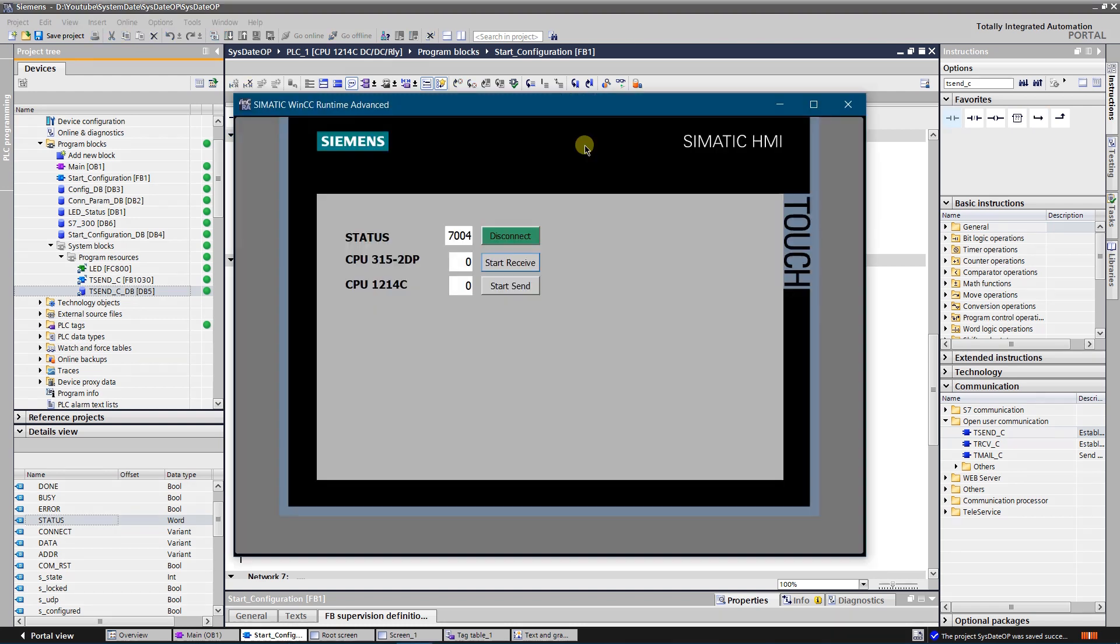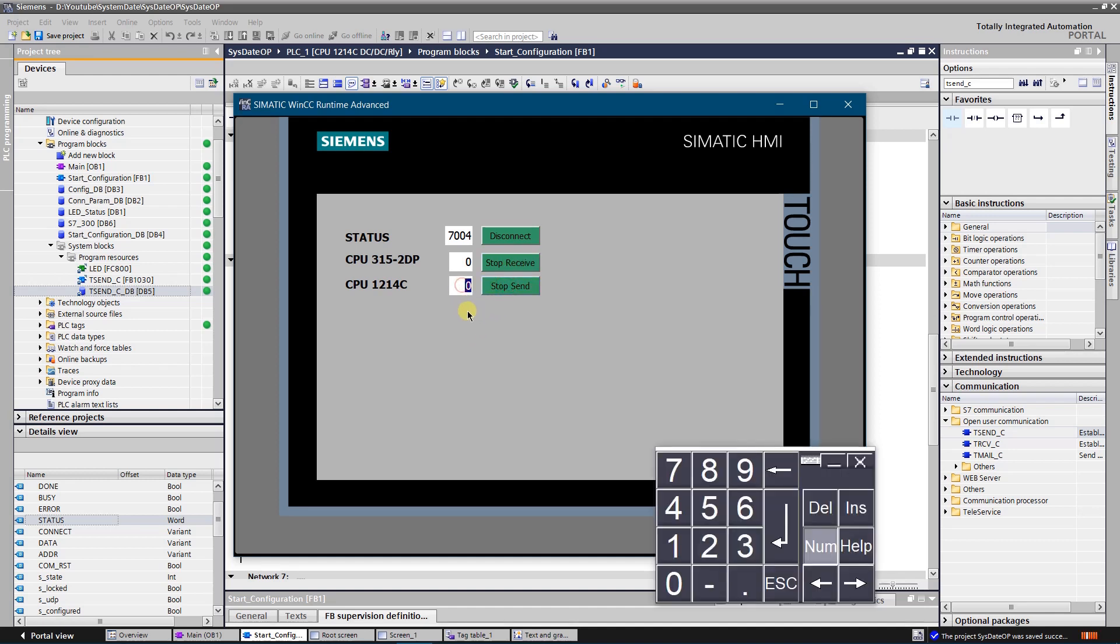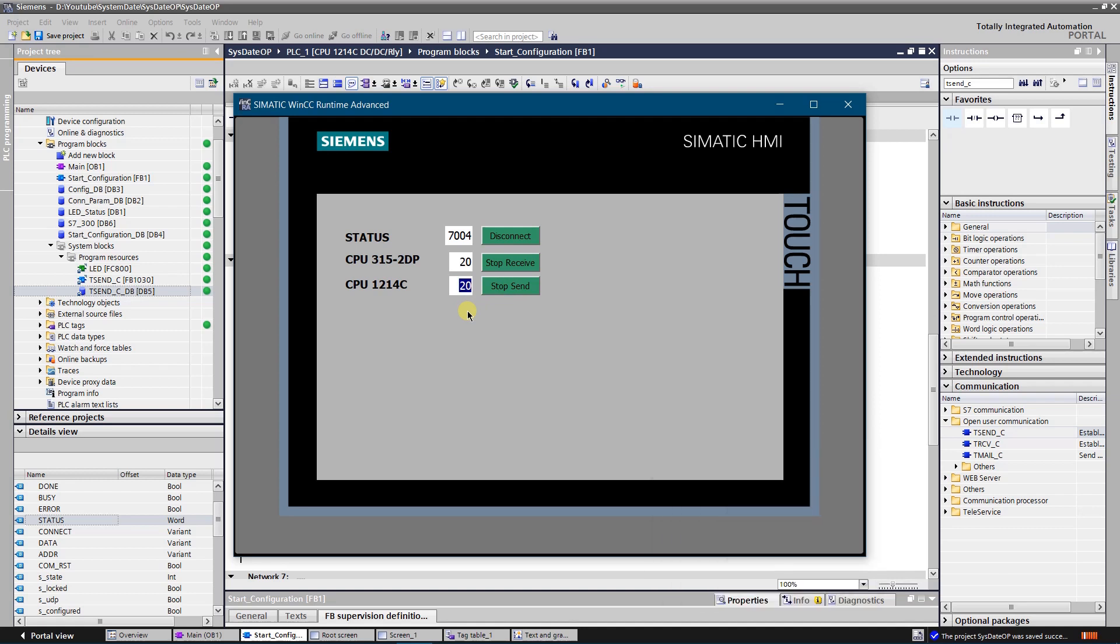Let's try to send some data to the S7-300 series station. Start the receive on the S7-300 side. Now let's try to send some value. As you can see, S7-300 station have got the value that I have sent from S7-1200 station.